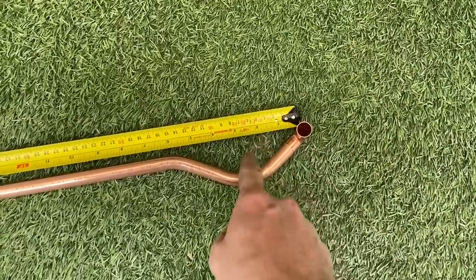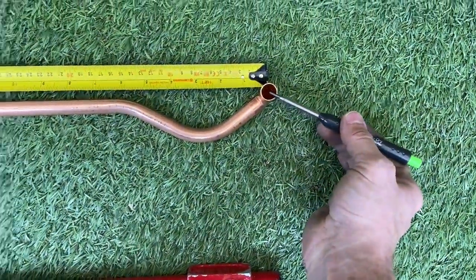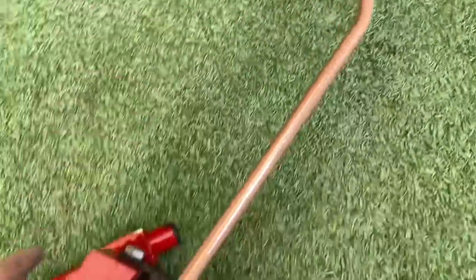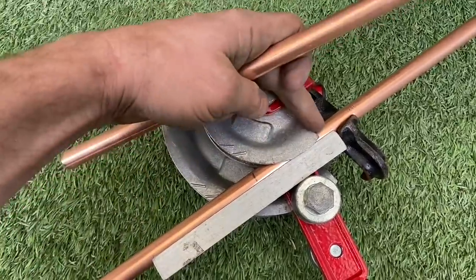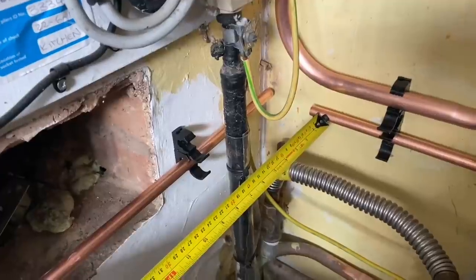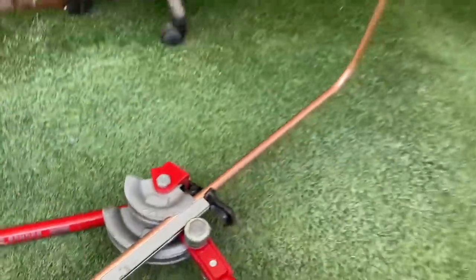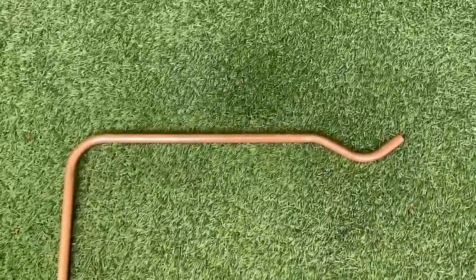There's our bend going up over the gas pipe, and then our bend that comes this way — it's 53 and a half from the center of the cold where it goes up. My next bend is going to go this way, measured from the center of this pipe where it comes up — that's to the inside edge. I just offer it in so there's my inside edge, then pull another 90. My last measurement comes from here to this inside pipe, then one last 90 bend. Make sure it all looks like it's lined up — tweaking a bit, holding the bender up straight helps.